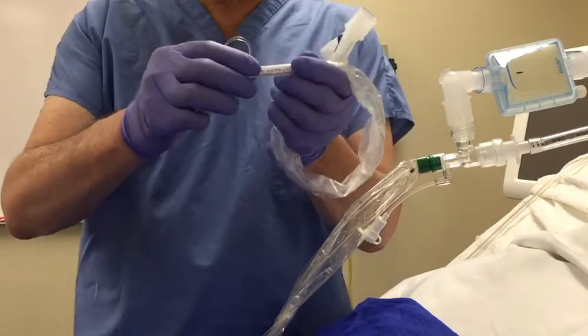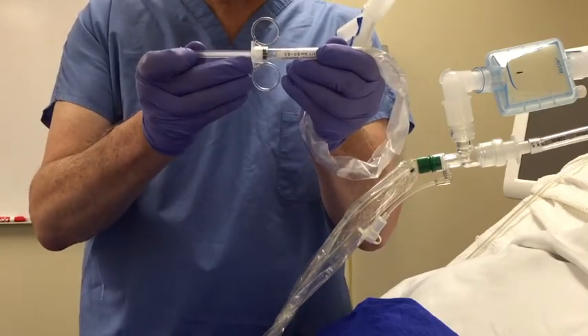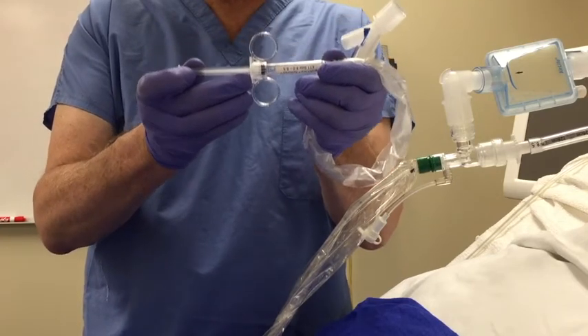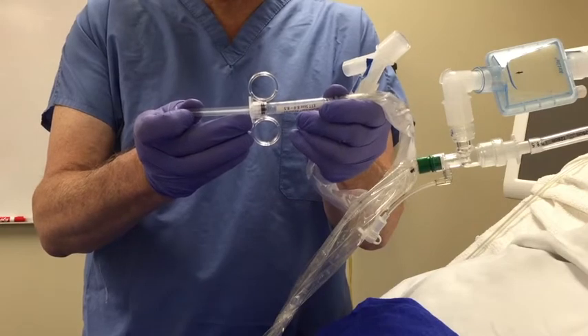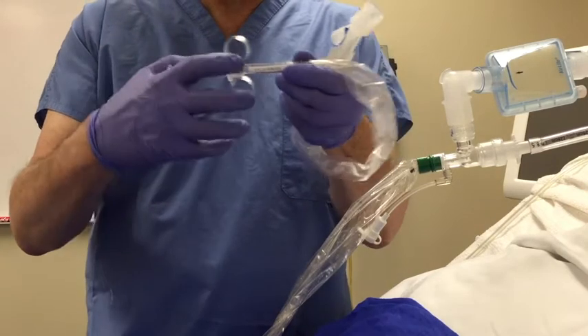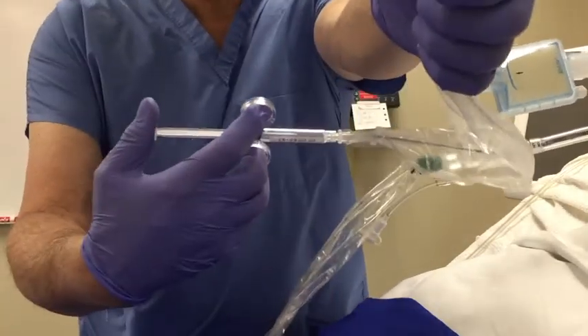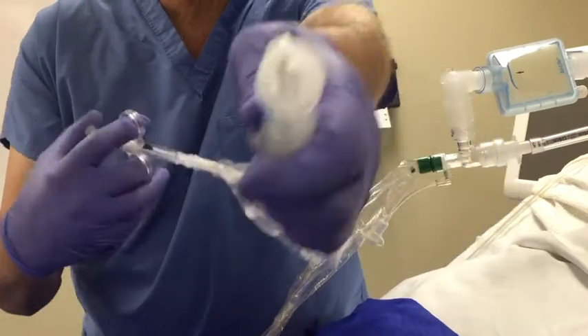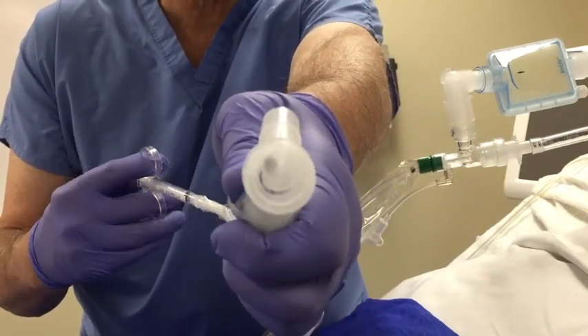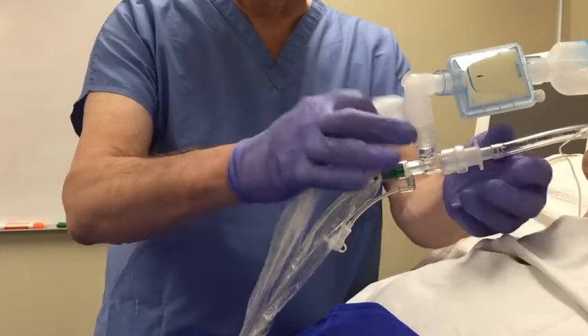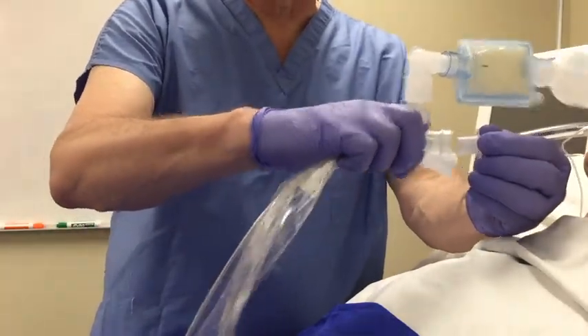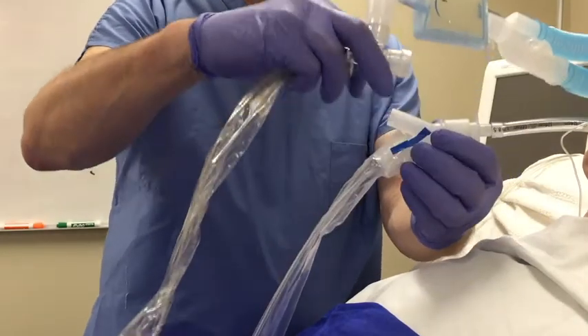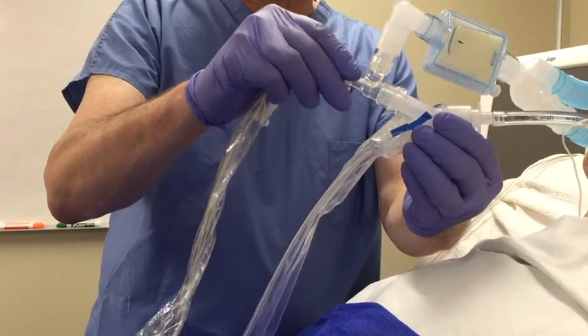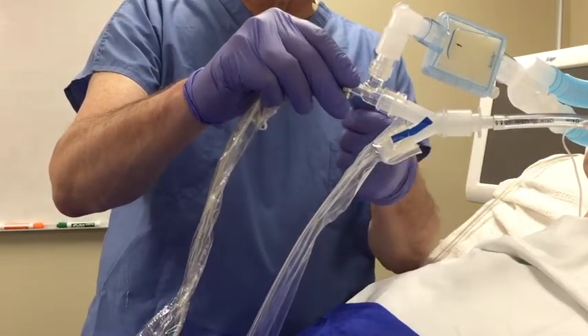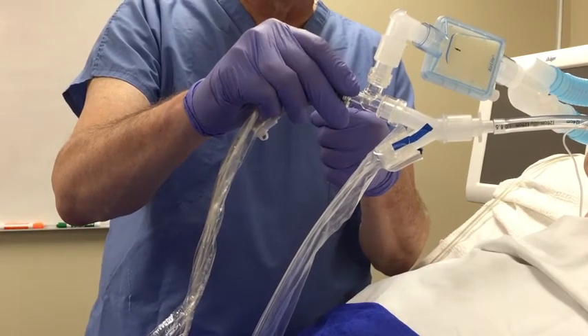To test the device, first, the syringe is pulled all the way back. This fills the syringe with the predetermined volume required in order to clean that size tube, which in this case is an 8.5. The syringe is then depressed all the way, and the distal end of the device is reviewed to assure expansion. Next, the closed suction system is disconnected from the endotracheal tube, and the Restore 2 adapter is inserted. The closed suction system is then reconnected to the adapter. The patient is now again being ventilated, and any time pressure for completion of the cleaning procedure has been eliminated.